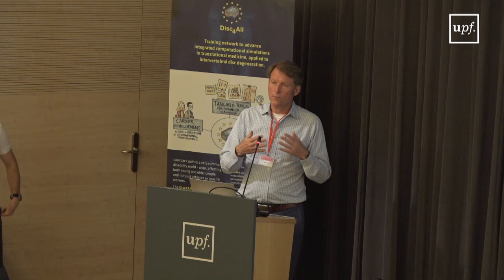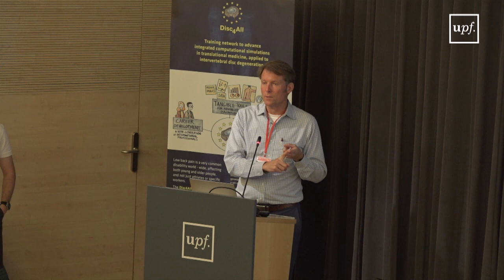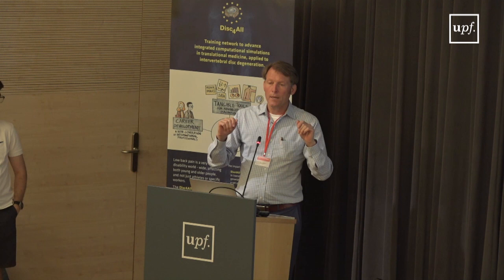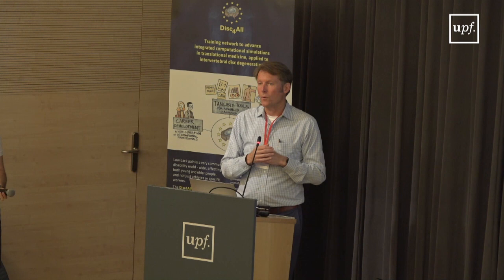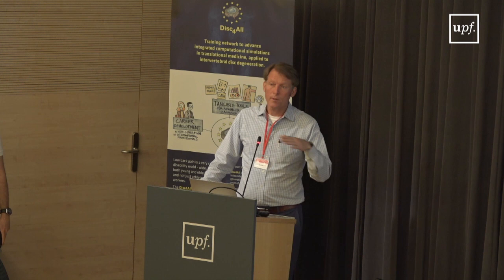So in that case, there was an engineering model summary and a statistical model summary. And then it was submitted to the center, just through normal channels and then sent to teams within the FDA who reviewed both of those applications and provided feedback. They did not know this was a mock submission until they came into the room and found out it was a mock thing. They were blinded to the fact it was a mock submission. So it was pretty rigorous in terms of that process.